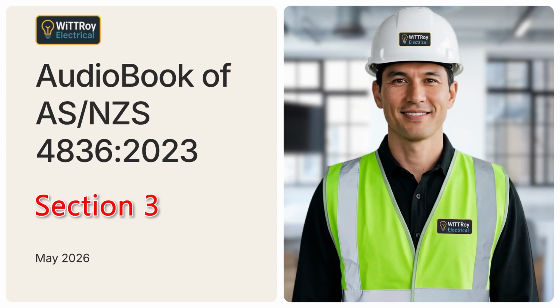Clause 3.2. Fault finding and testing. Clause 3.2 explains fault finding and testing. Before fault finding begins, a visual inspection and assessment of possible component failure must be carried out. The purpose is to decide whether the fault finding can be done with the installation or equipment de-energized.